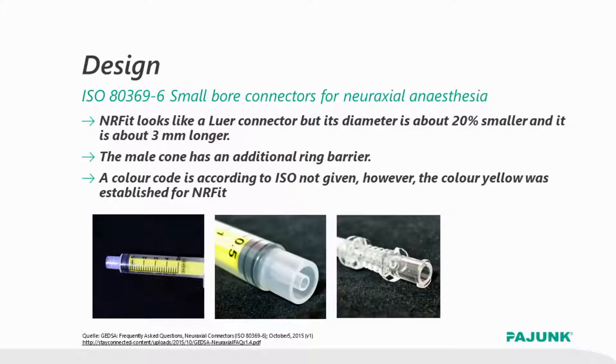What does NRFit mean? This is quite simple. The diameter of connectors is reduced by 20%. As a result of this reduced diameter, Luer and NRFit components cannot be connected with each other anymore.